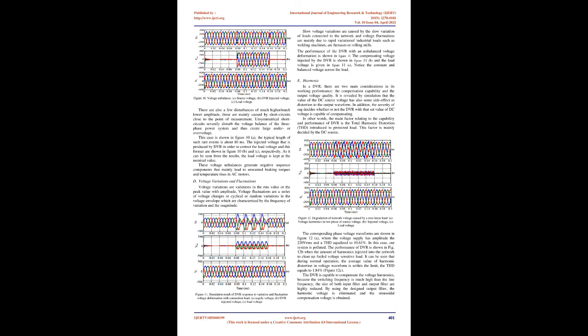B) Over voltage. Next, the performance of the DVR for a voltage swell condition is investigated. Figure 8. Two-phase voltage swell: A, source voltage; B, injected voltage; C, load voltage. In this case, two of the three phases are higher by 30% than the third phase, as shown in Figure 8A. The voltage amplitude is increased about 30% of the nominal voltage.